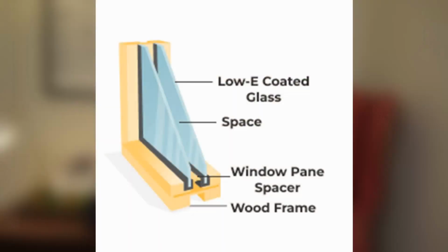Now let's say you've designed a site-built fixed glass window with 2 panes of low-E glass and a 1-inch airspace between. Each pane of glass has a U value of 0.36, and the airspace has an R value of 3.6. It's kind of funny how the numbers worked out there in this example, isn't it? Well, when the plan reviewer or your HERS rater asks what the total U value of the window assembly is, here's how you calculate it.